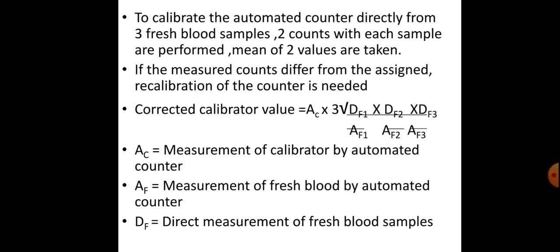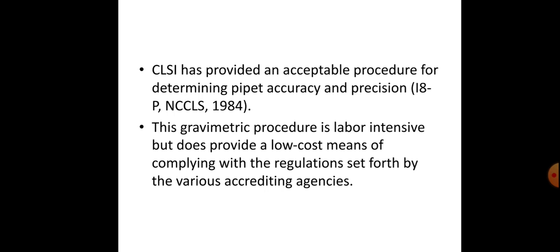To calibrate the automated counter directly from 3 fresh blood samples, 2 counts with each sample are performed, and the mean of the 2 values is taken. If the measured counts differ from the assigned values, recalibration of the counter is needed. The corrected calibrated value is taken using this formula: AC times DF divided by AF, where AC is the measurement of the calibrant by the automated counter, AF is the measurement of fresh blood by the automated counter, and DF is the direct measurement of fresh blood samples.